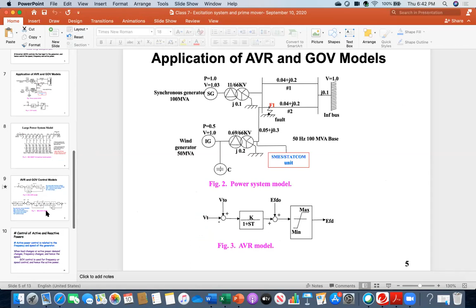Moving forward, control of active and reactive power. We already discussed control of active and reactive power, and concluded that active power control is related to the frequency and speed of the generator. When load changes or active power demand changes, frequency changes and hence the speed. Customers continuously change loads, which impacts active power, and hence affects frequency and then speed. Governor control is used for frequency, speed, and hence active power. We already covered this.